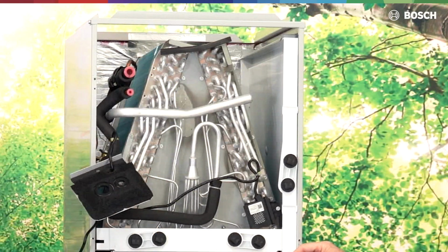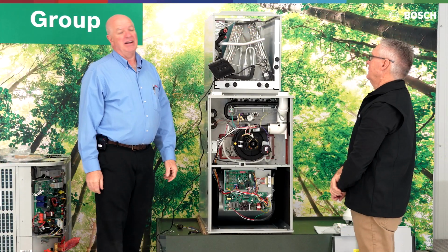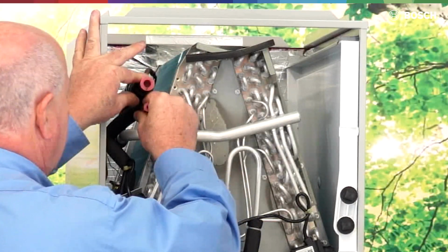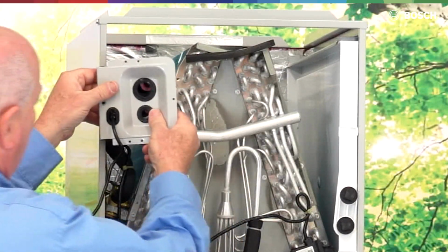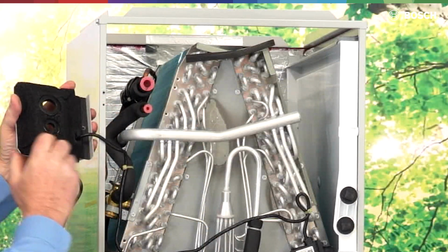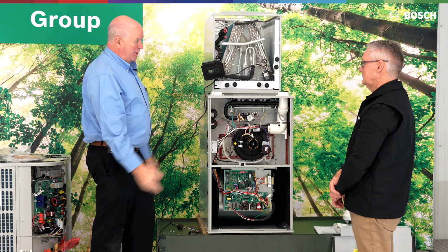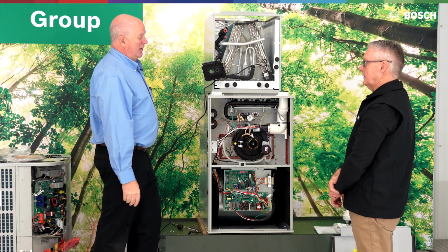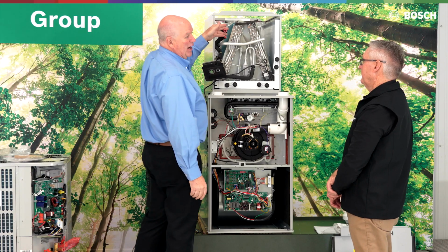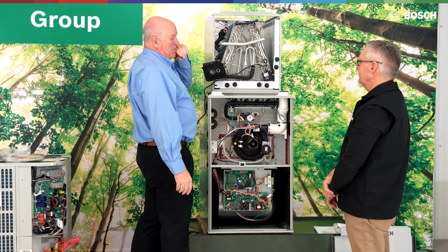Wow. So our fittings are inside, and the issue comes when you braze: you have to wrap these with a rag and protect the inside. When I do my work, I'll slide this all the way over to the line set. That leaves this wide open, and I can do my braze. I am a turbo tip person, not oxygen acetylene. So you've got to watch your heat. Those are flamethrowers. Exactly.